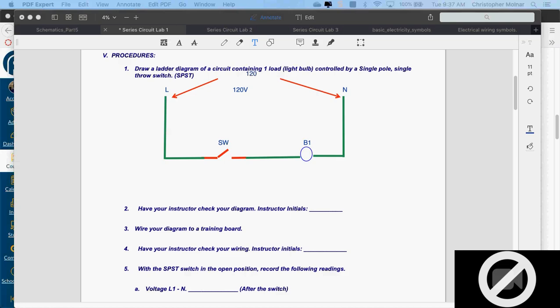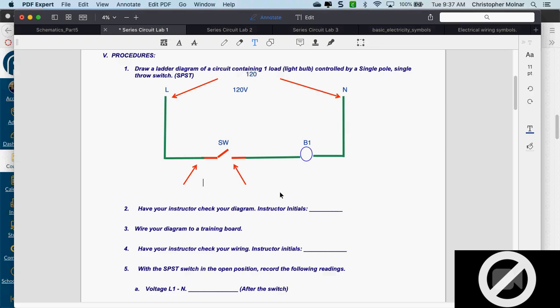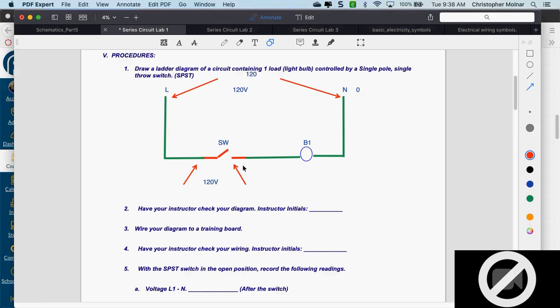If I take a voltage reading across the open switch from line side to neutral side, I'm going to get 120 — voltage across an open switch is source. If I take a voltage reading from the load side of the switch to the line side of the bulb, the reading is zero because I'm on the same side of the open switch. Both points are after the open switch — no difference in potential.